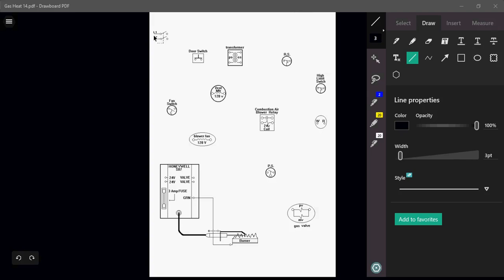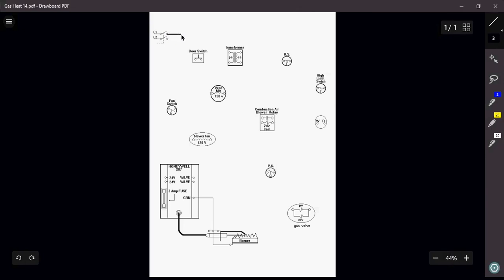So how do we wire that? Well, here we go. We've got L1 and neutral, or L1, L2. When we are wiring this, obviously we have to start off with L1, because L1 is what's bringing power into our furnace. Out of L1, I want to bring that power down into my door switch. Out of that door switch, usually when you're looking at a furnace like this, it's probably going to go right into a transformer. That transformer could be mounted right on a circuit board. If it's a newer model type of furnace, then you might just have a transformer mounted inside the furnace itself.